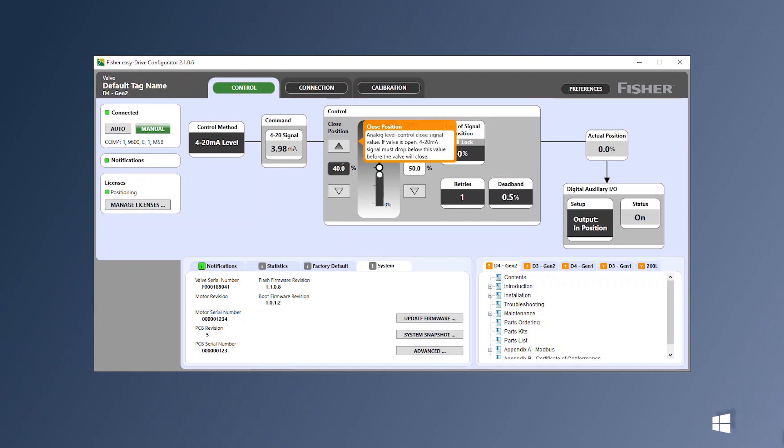If the valve is closed, it will not open until the signal is above the open position, at which point the valve will open to that level and modulate normally. The valve will then close when the signal drops below the closed signal and not reopen until the open signal has been reached.